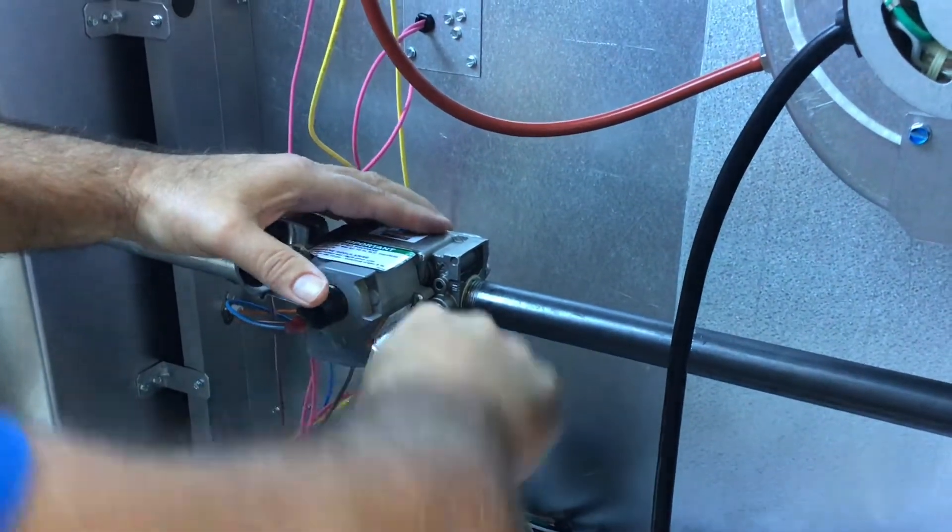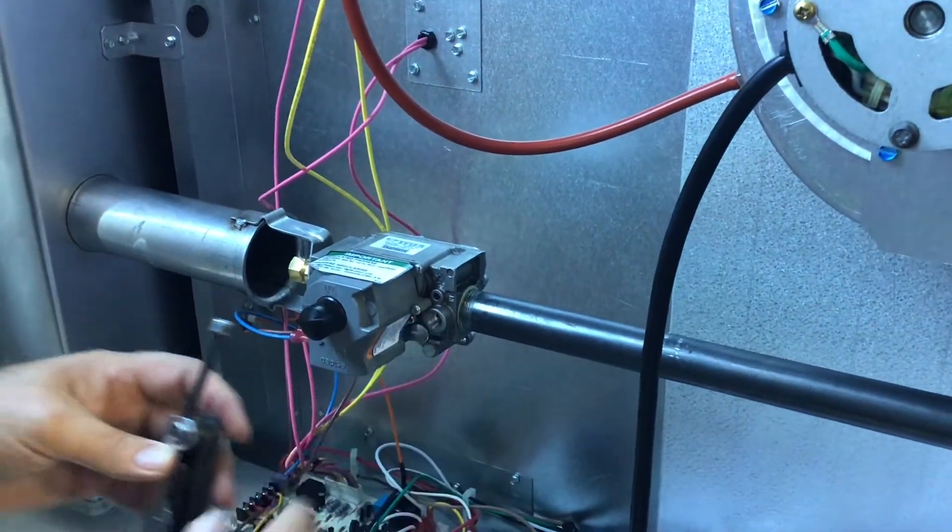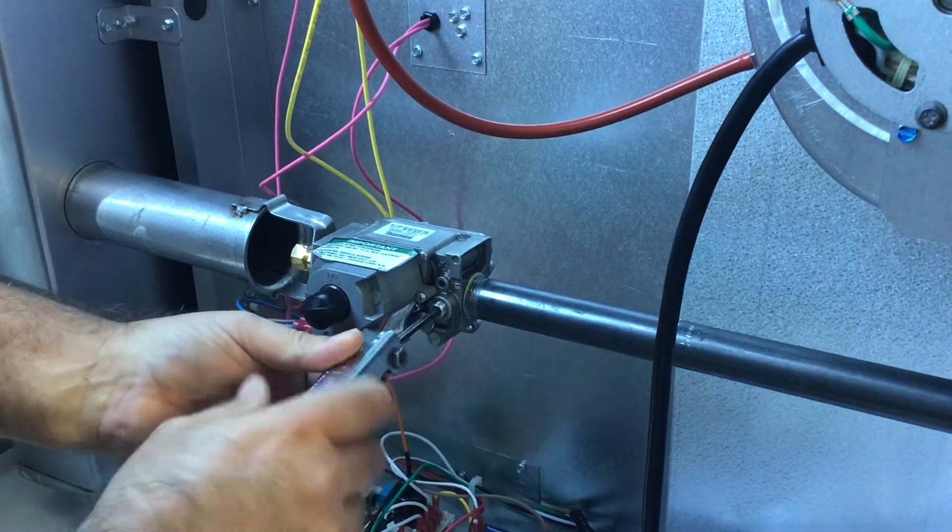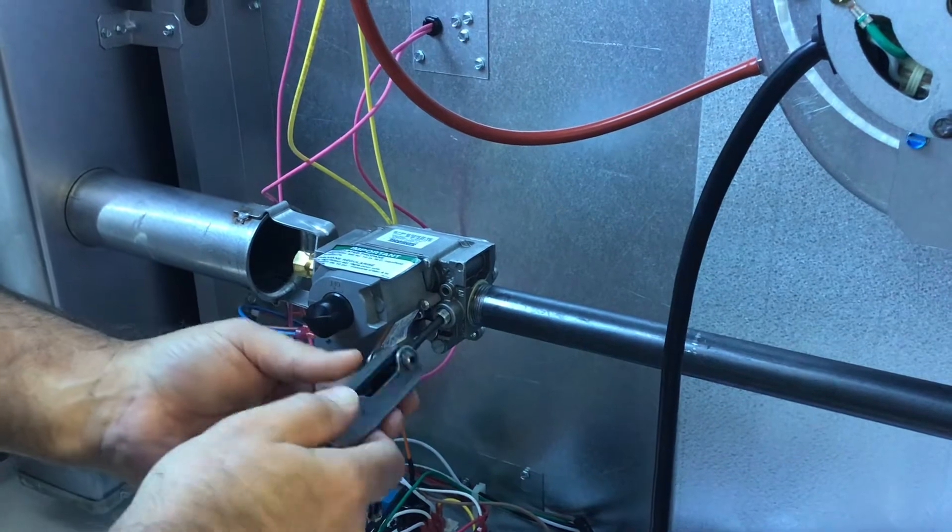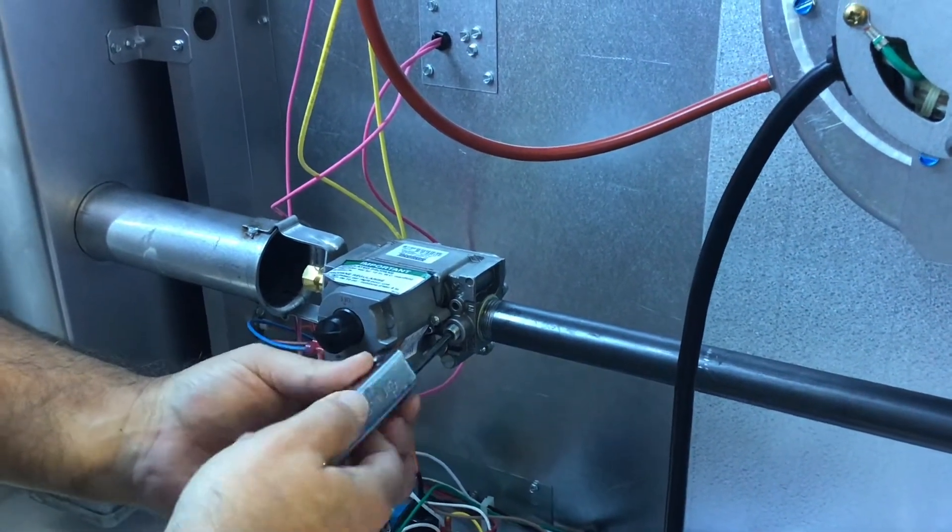Remove the Allen key as such, insert your manometer and we're going to look for no more than 13.5 inches inlet at this point. That's the maximum you can have.